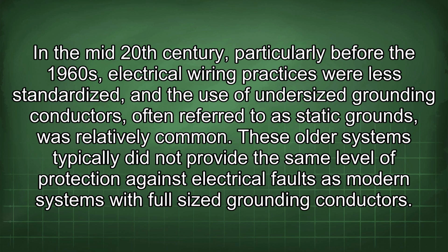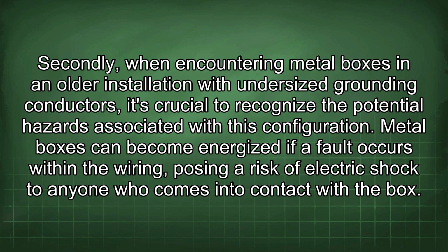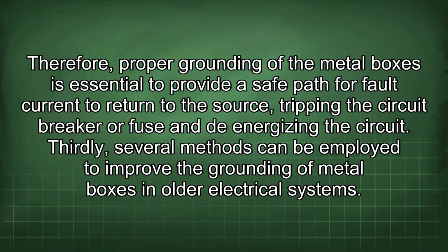These older systems typically did not provide the same level of protection against electrical faults as modern systems with full-size grounding conductors. Secondly, when encountering metal boxes in an older installation with undersized grounding conductors, it's crucial to recognize the potential hazards associated with this configuration. Metal boxes can become energized if a fault occurs within the wiring, posing a risk of electric shock to anyone who comes into contact with the box. Therefore, proper grounding of the metal boxes is essential to provide a safe path for fault current to return to the source, tripping the circuit breaker or fuse and de-energizing the circuit.